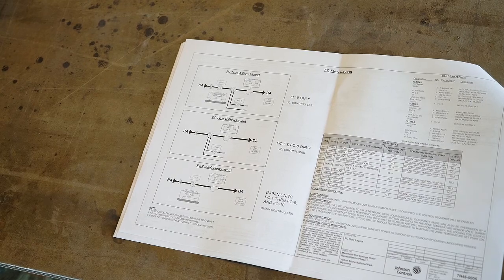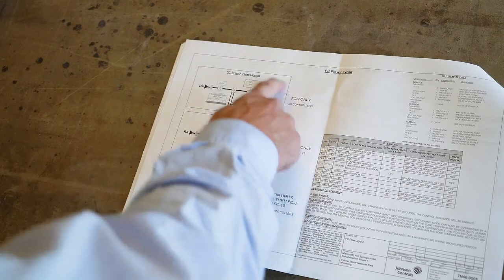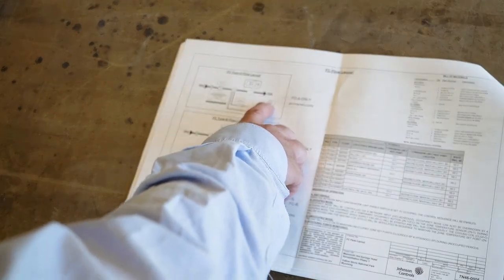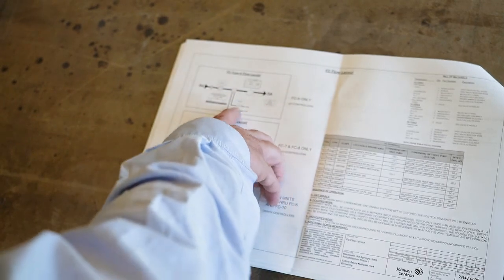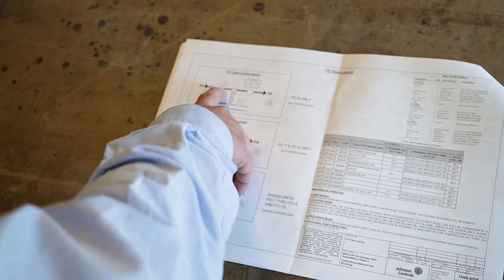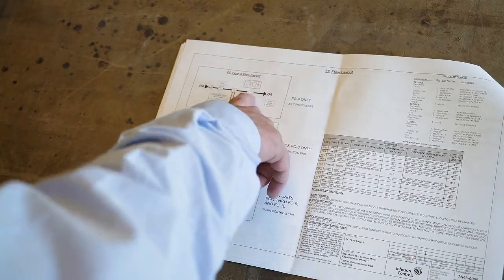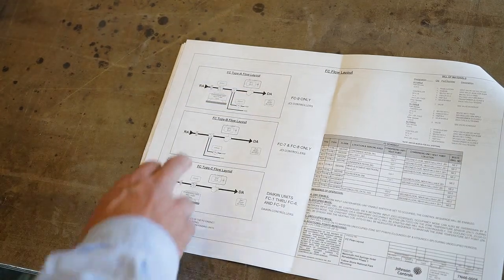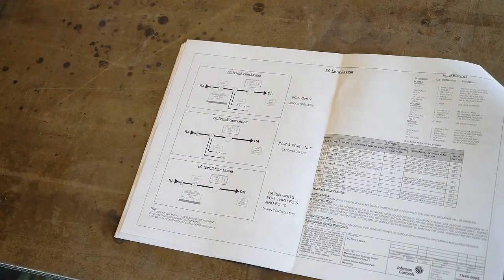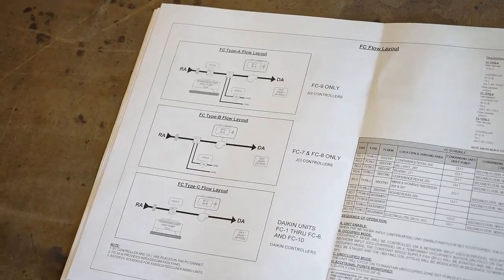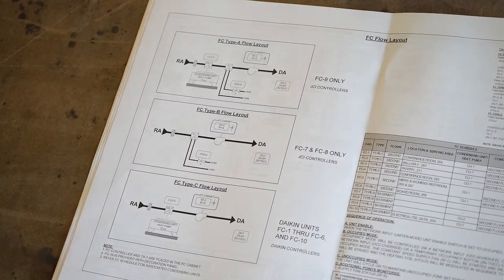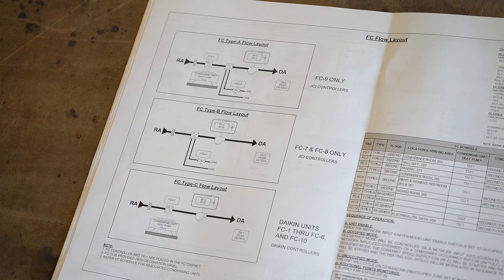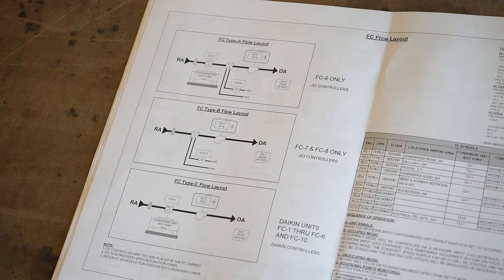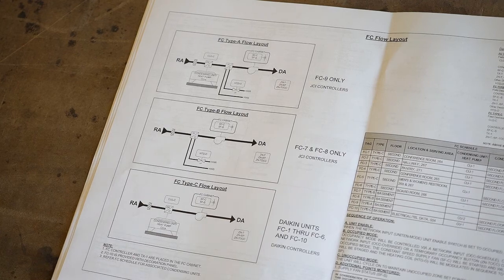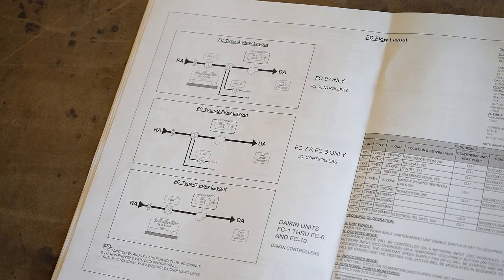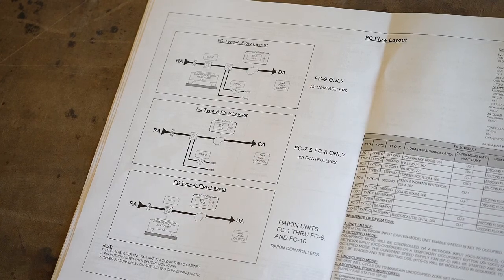We have, and if you look at this drawing, let's just look at number 9, which is this unit right here. So here we're using a zone temperature sensor and a set point, which we have a temporary occupied on it. And then we have the hydronic heating coil valve. And then we have the condensing unit up on the roof for cooling. And then we have the command and status on the fan coil unit downstairs. So we're controlling this unit individually. So when we go to occupied, the first thing we do is turn the fan on. We make sure we have status, and then we look at the room temperature and see how far we're off set point, and then determine whether we just stay in satisfied or we go to heating or cooling. And then we either modulate the heating valve to get to room temperature, or we start staging on the condensing unit for cooling. And that differential from set point, is how many degrees as far as?